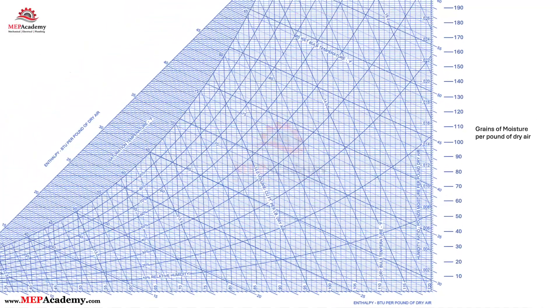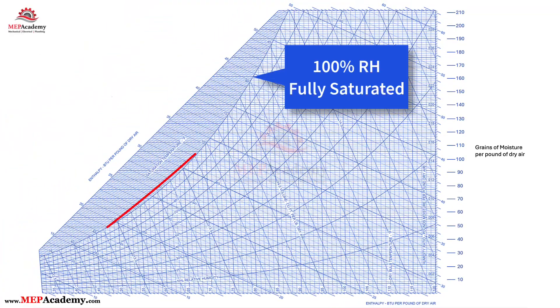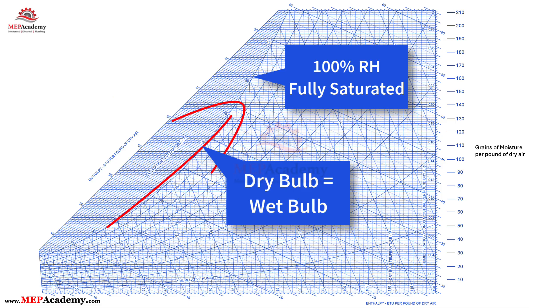The curved upper boundary is the saturation curve. That's 100% relative humidity. This outer curved boundary is called the saturation curve. It represents 100% relative humidity, air that is fully saturated with moisture. Along this curve, the dry bulb temperature and wet bulb temperature are equal. At any point on the saturation curve, the air cannot hold any more water vapor without condensation occurring.